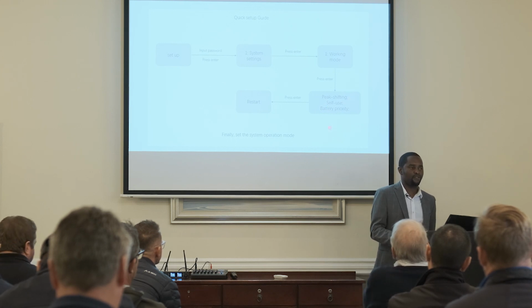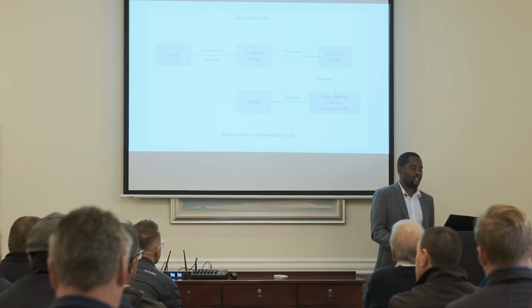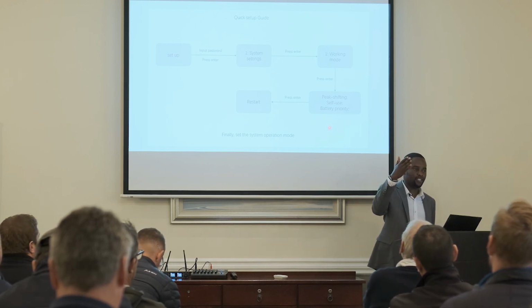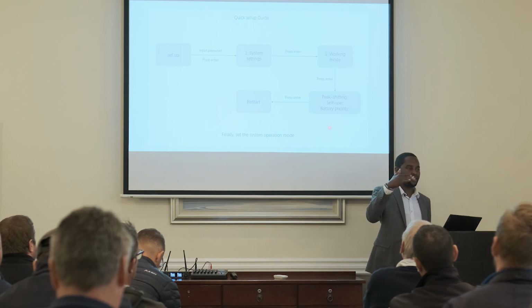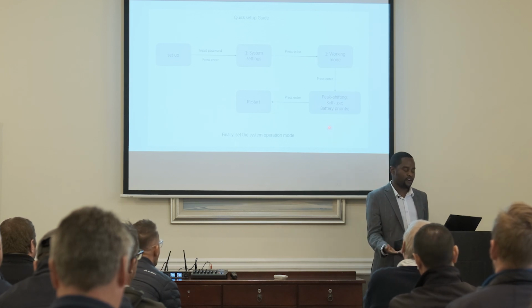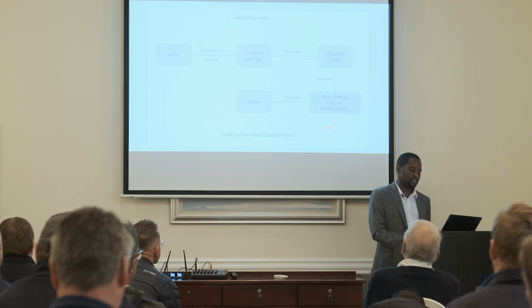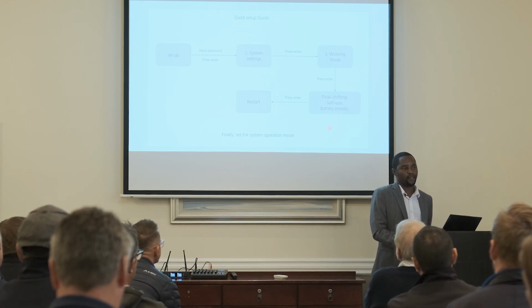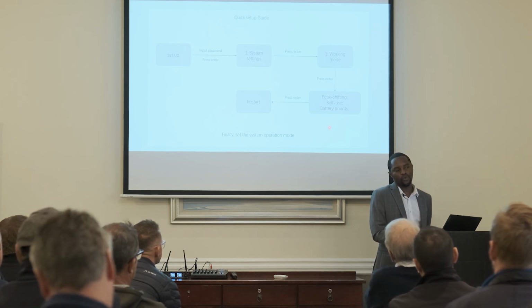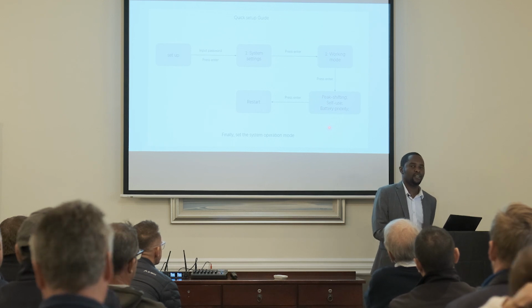Then the self-use, this is the maximum self-sufficiency, where you actually use your system. That's when you get through that work mode. Say PV first, right? If PV is not available, my battery can discharge. If that is not enough, I can take from grid. If grid is not available, then I can start my generators. So this is the self-consumption, the self-use. Then the battery priority. You can choose now, during the morning, you've got the little PV that we get: do you want it to go to the loads or do you want it to charge your batteries fully? I'm sure with the installers, there's a different school of thought there.